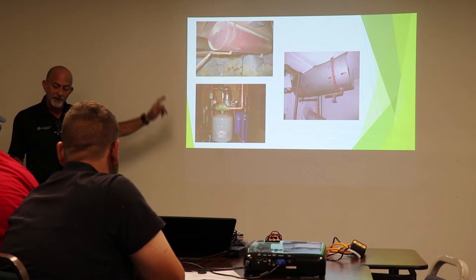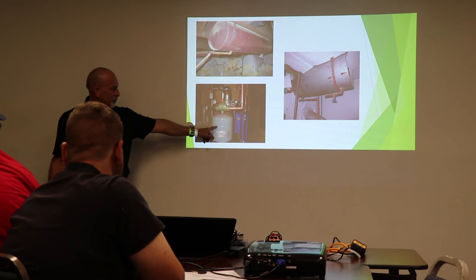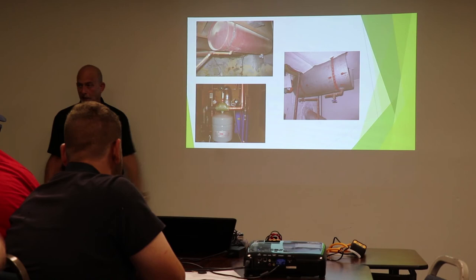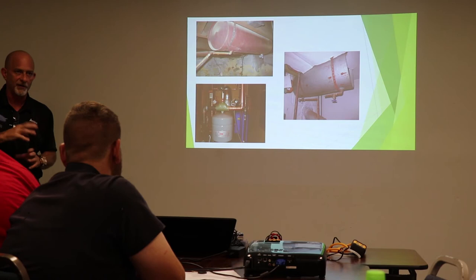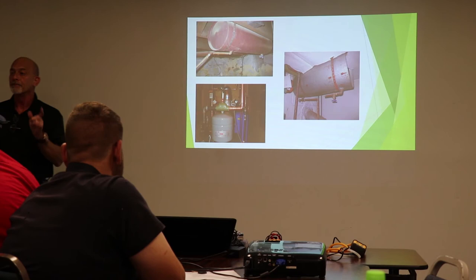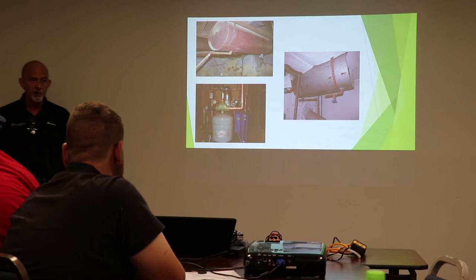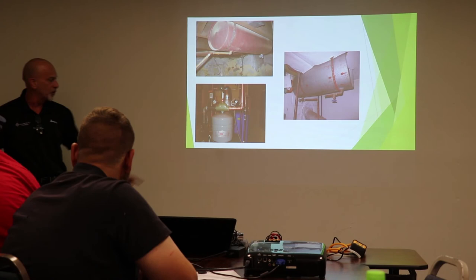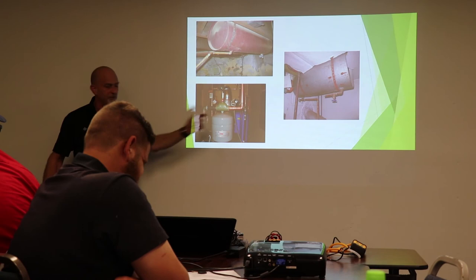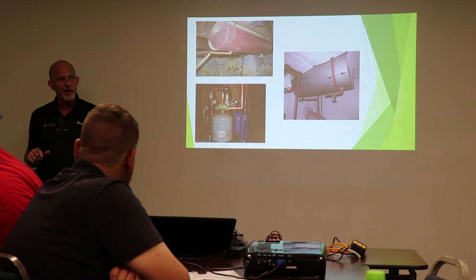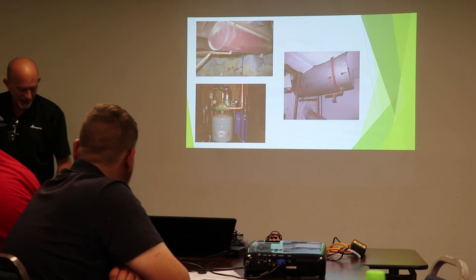the better. If you do have to change one of these that doesn't have a shutoff valve in here, here's what I recommend. Get your new tank. Be nice to the next guy. Get a shutoff valve. Get it ready to go, ready to spin up in there. Loosen that one up. Get to about a turn left to go. Every water boiler has a drain valve in it. If you open that drain valve, you cut pressure in the system. You can spin that off, spin the new one on, close your drain valve in a matter of no time flat, and you won't get soaking wet. You may get a little bit on your pant legs or maybe a little bit on your shirt, but you're not drenched. So keep that in mind.